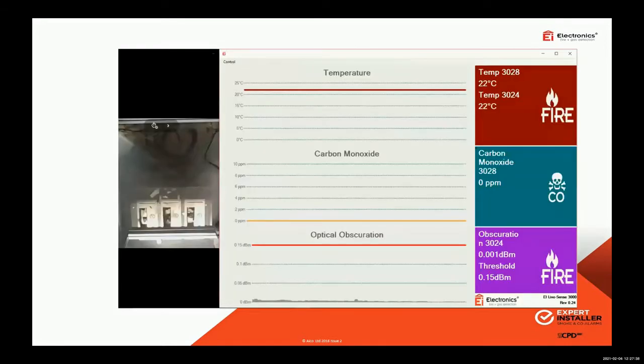I have a video here to try to get the message of this unit across a bit better. If you look at the left-hand side of the screen, you can see it's a fire generating chamber that we have down in the factory in Shannon. There are 3 different sections there, 3 different openings. So we're looking from the top of the chamber down to the very bottom. On the left-hand side, you'll see in a second where we generate a fire. Where we're looking from the top of the screen, down into that chamber, is where the smoke detectors are located.